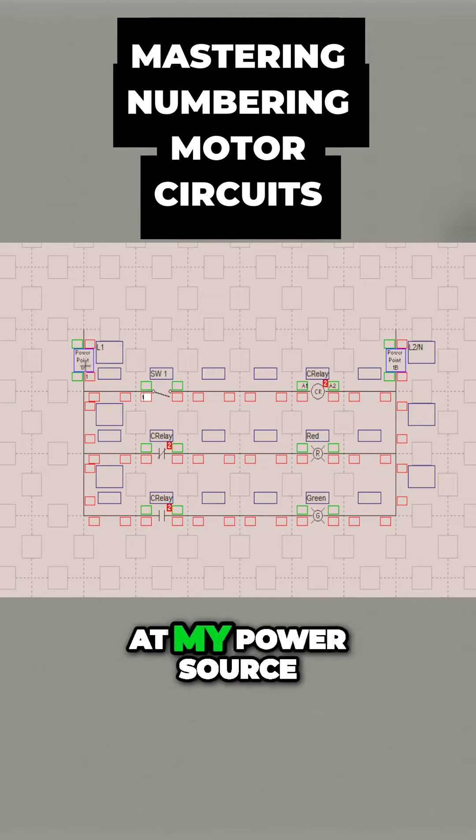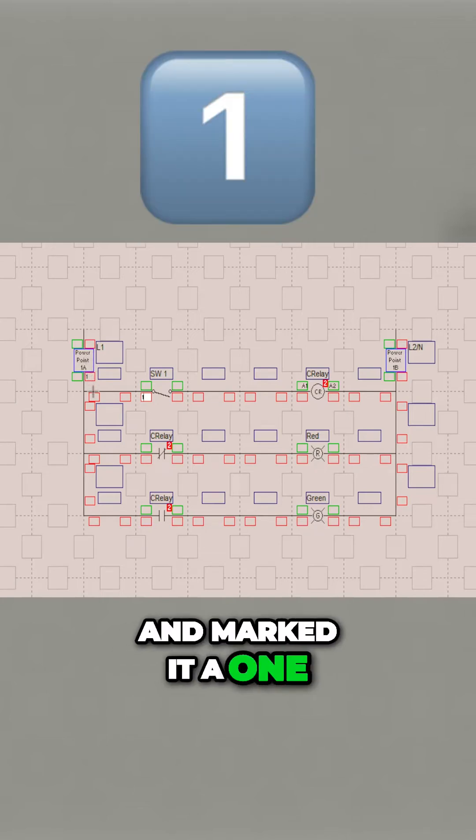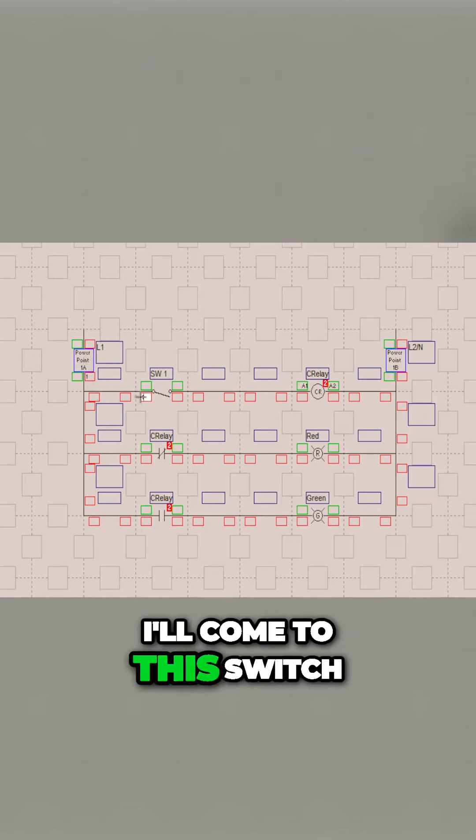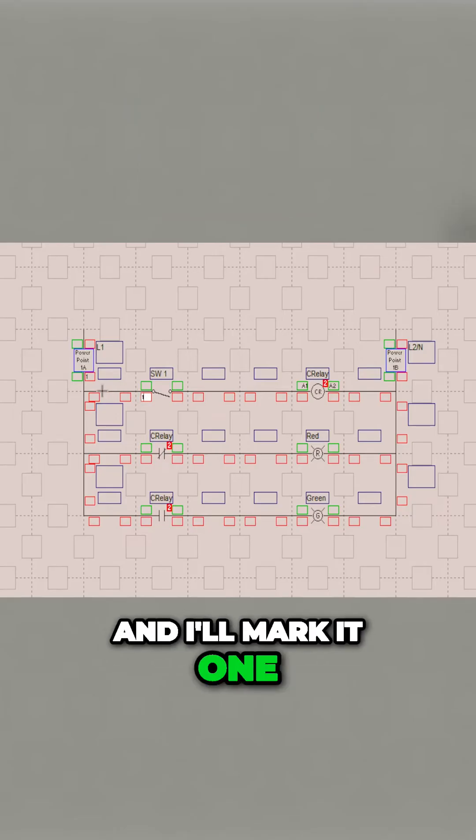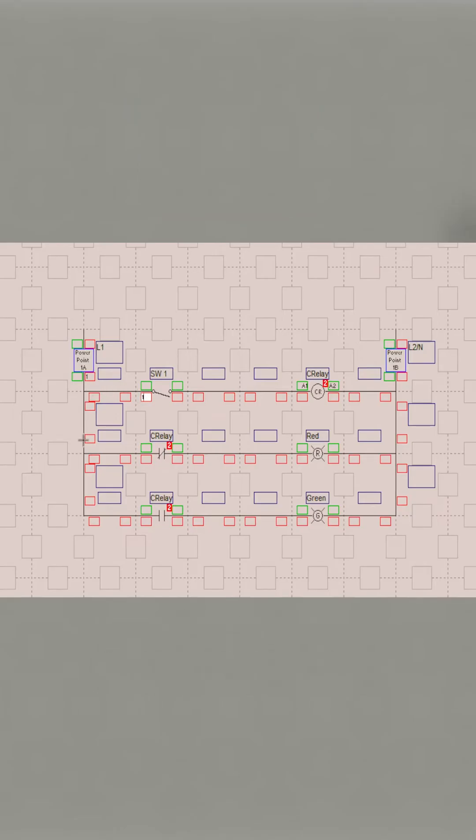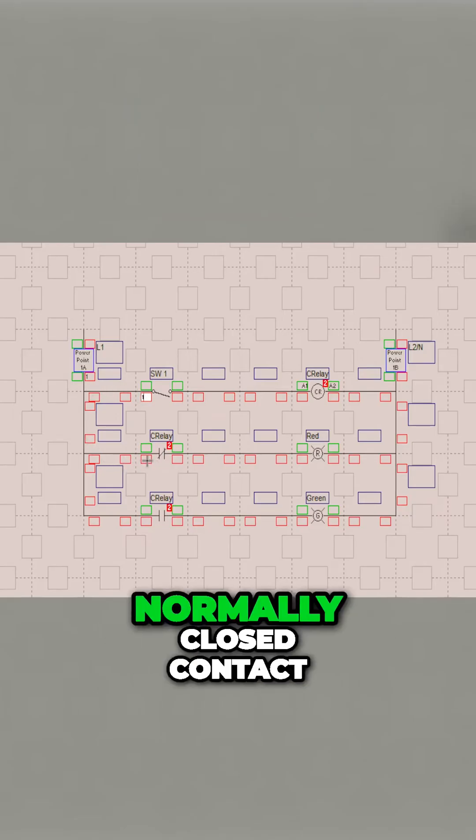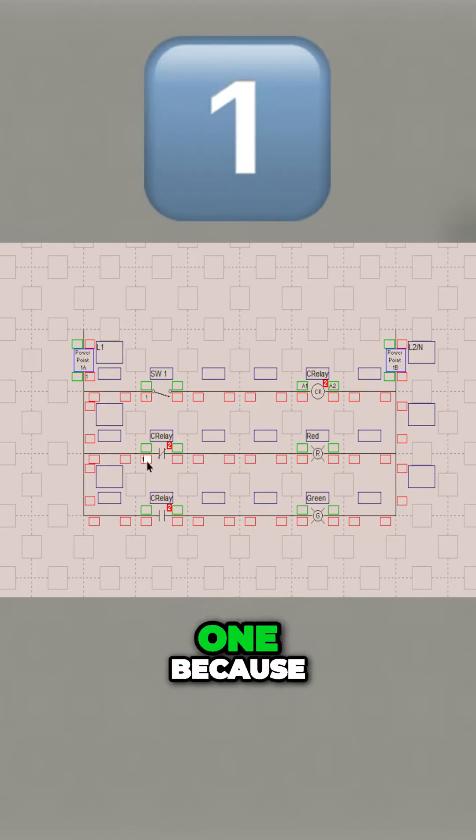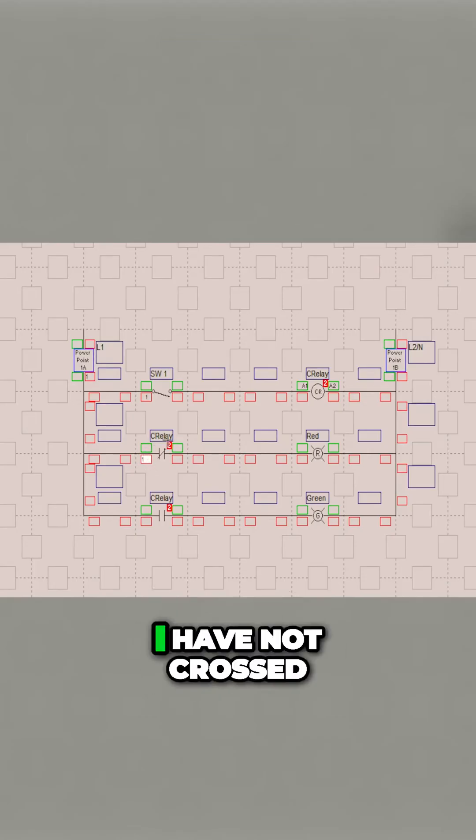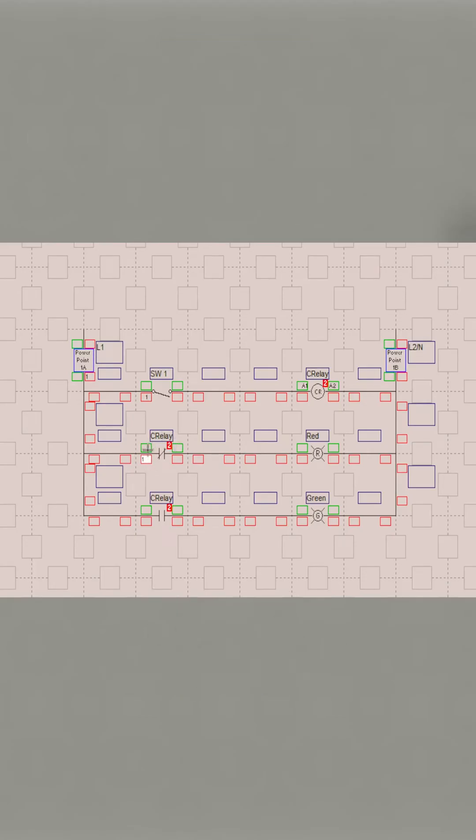I went right there at my power source, marked it a 1, and I'll come to this switch and I'll mark it a 1. If I follow the hot down to this control relay normally closed contact, I'm going to mark it 1 because I haven't crossed over a component yet.